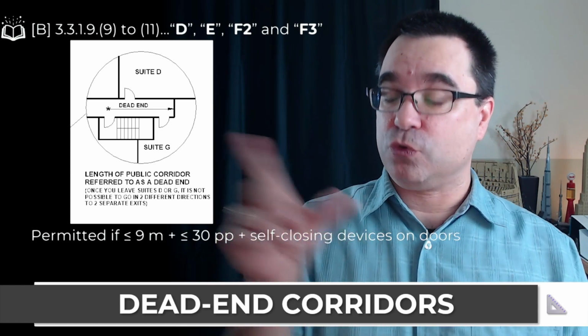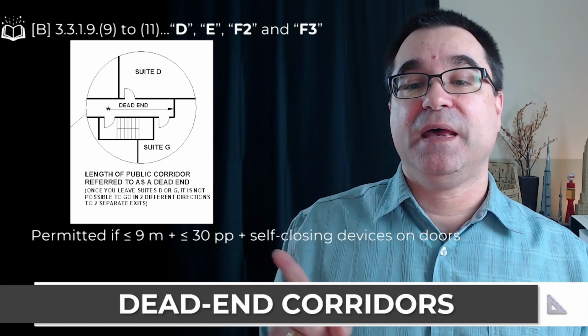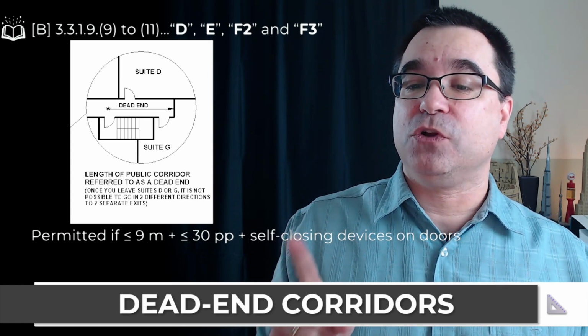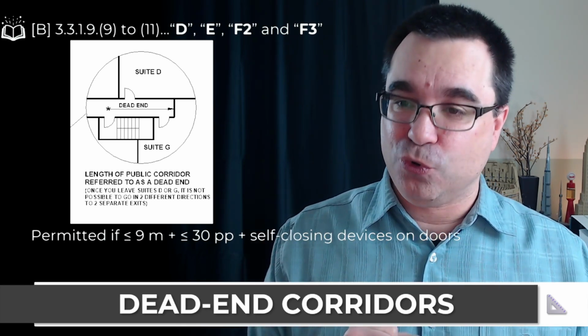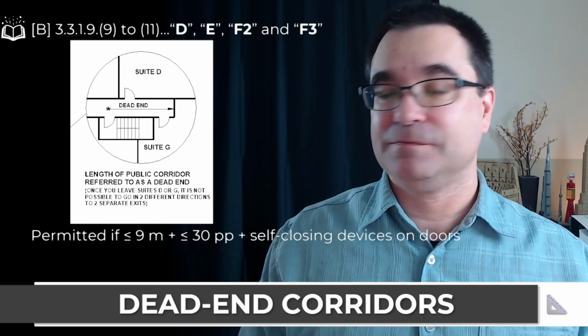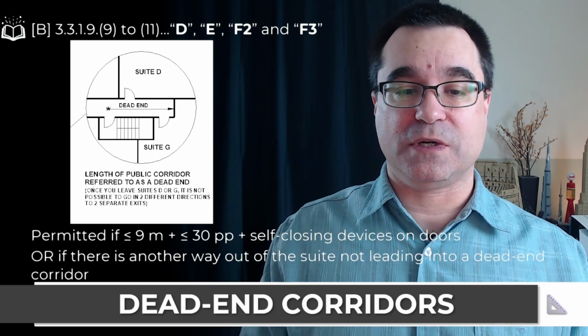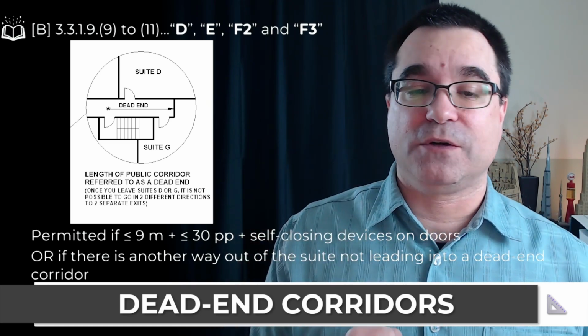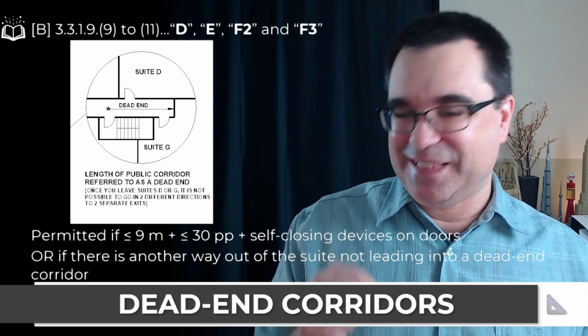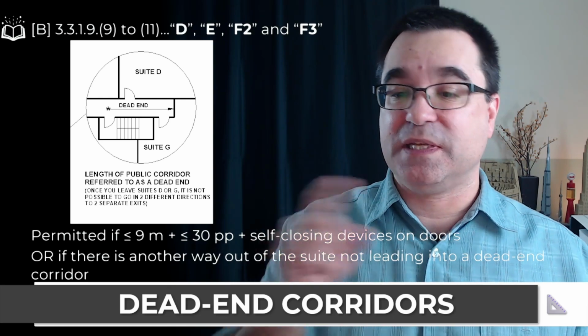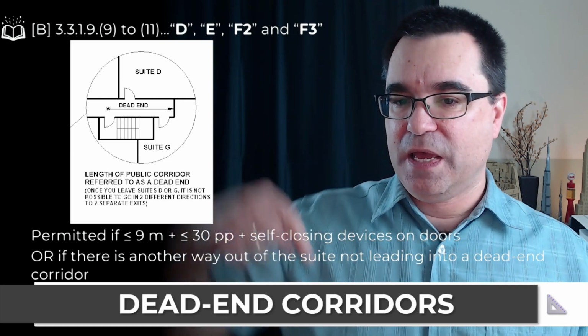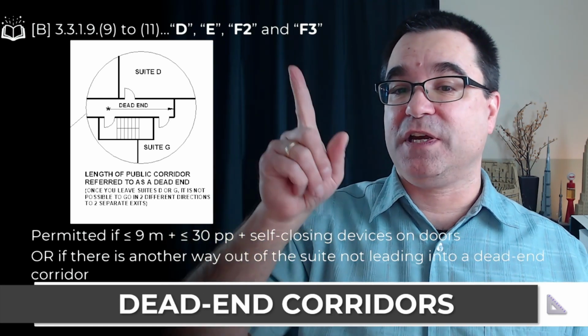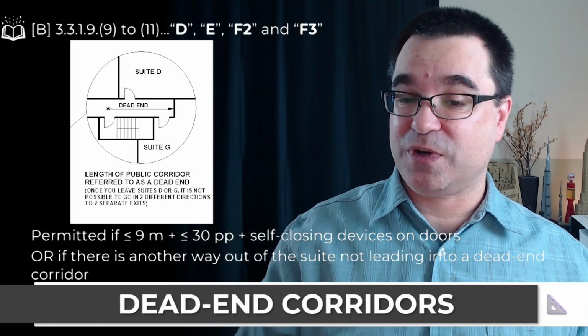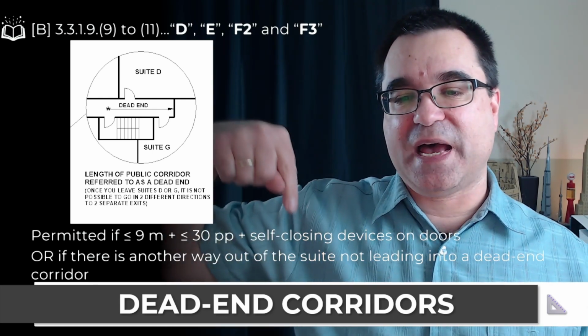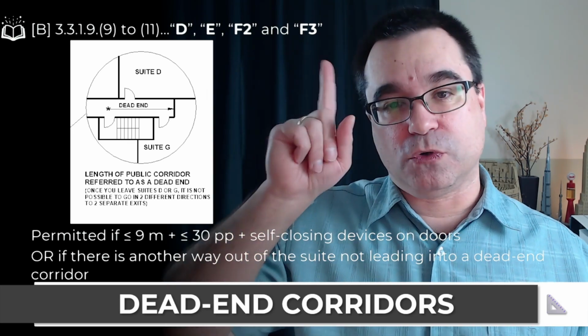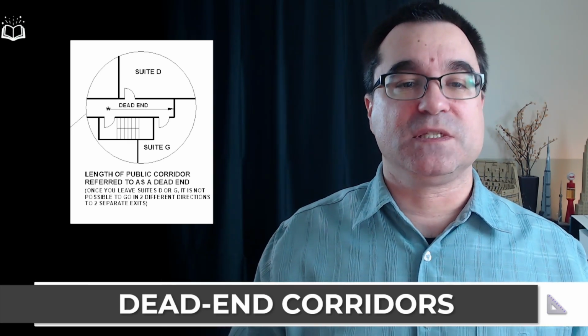If that dead-end corridor is for up to 30 people, and there are self-closing devices on the doors, okay? That's one way that dead-end corridors are allowed. Another way is if there is a second way to get out of those suites that does not lead into a dead-end corridor. But notice how these requirements are very specific and restrictive, okay? Only if these happen are you allowed a dead-end corridor in these major occupancies.